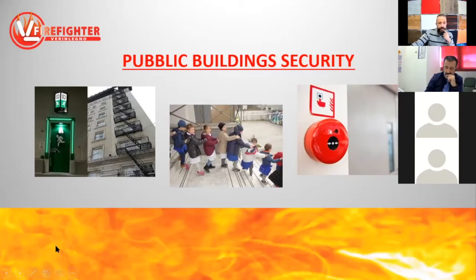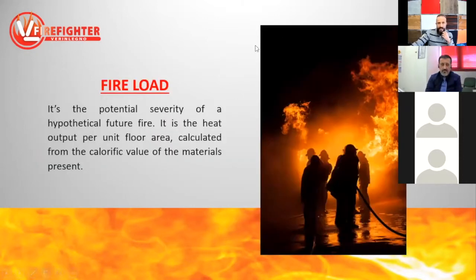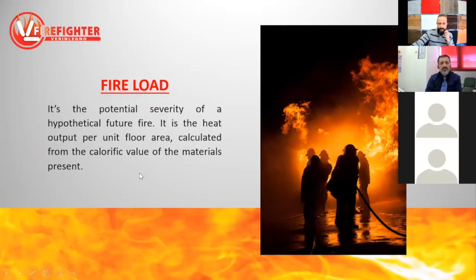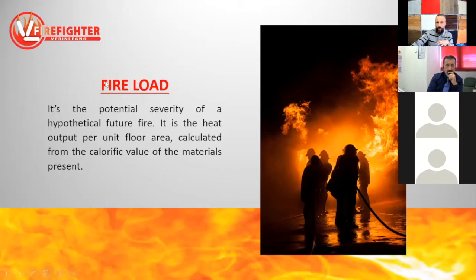The fire propagation depends on the fire load. What is the fire load? It's the potential severity of a hypothetical future fire. It is the heat output per unit floor area calculated from the calorific value of the materials present. So if a building has a high fire load, the propagation of fire will be very fast. At the contrary, if the fire load is low, the propagation will be slow and we will have time to evacuate the building. So how can we decrease this fire load?